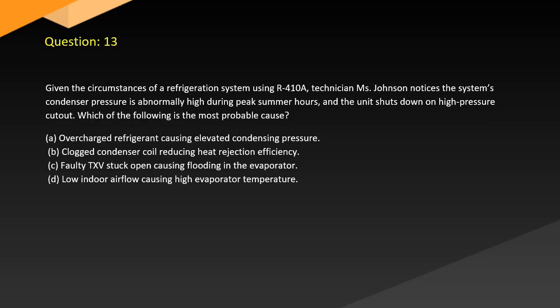Question 13. Given the circumstances of a refrigeration system using R-410A, technician Johnson notices the system's condenser pressure is abnormally high during peak summer hours and the unit shuts down on high pressure cutout. Which of the following is the most probable cause? A. Overcharged refrigerant causing elevated condensing pressure. B. Clogged condenser coil reducing heat rejection efficiency. C. TXV stuck open causing flooding in the evaporator. D. Low indoor airflow causing high evaporator temperature.